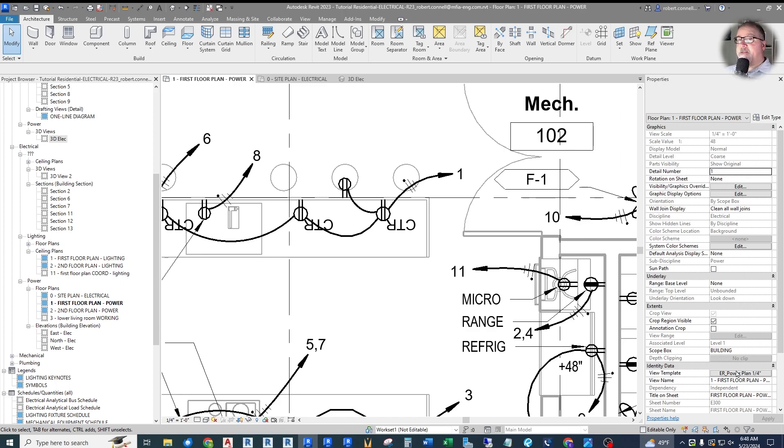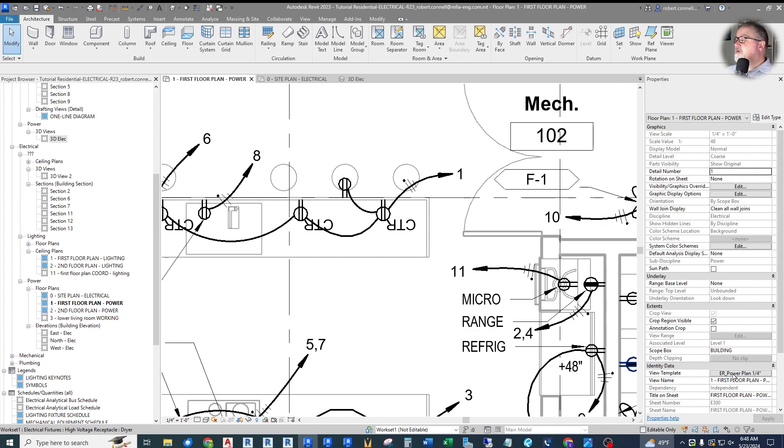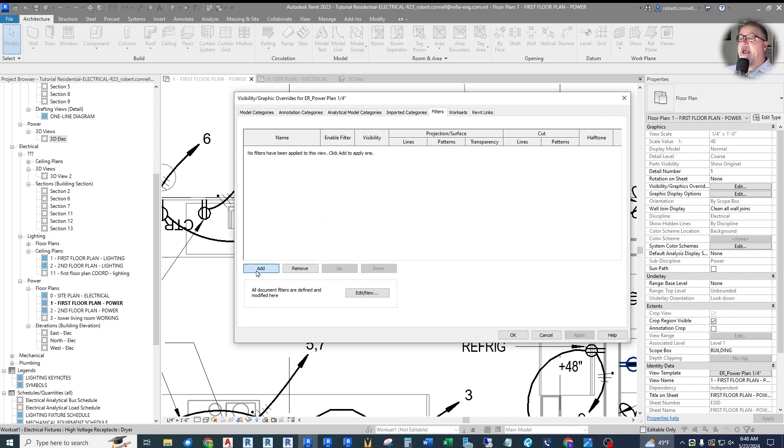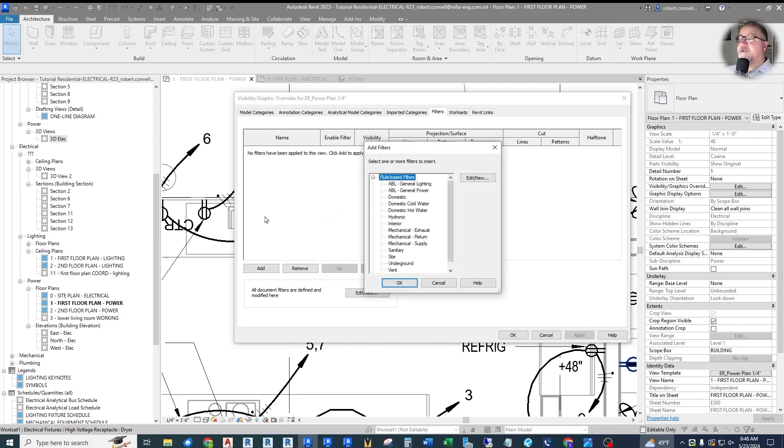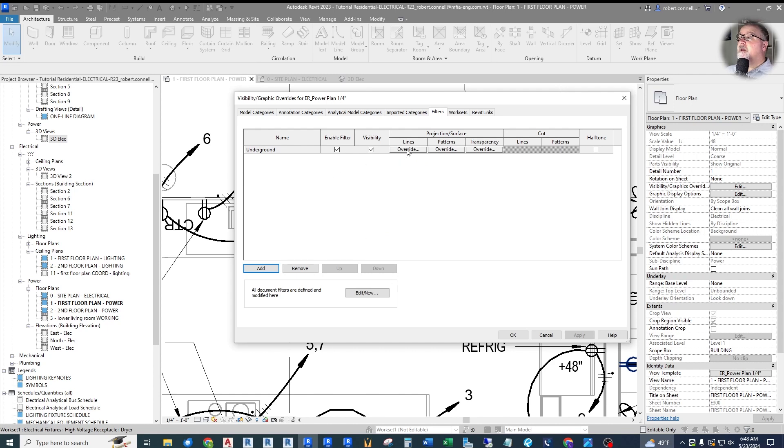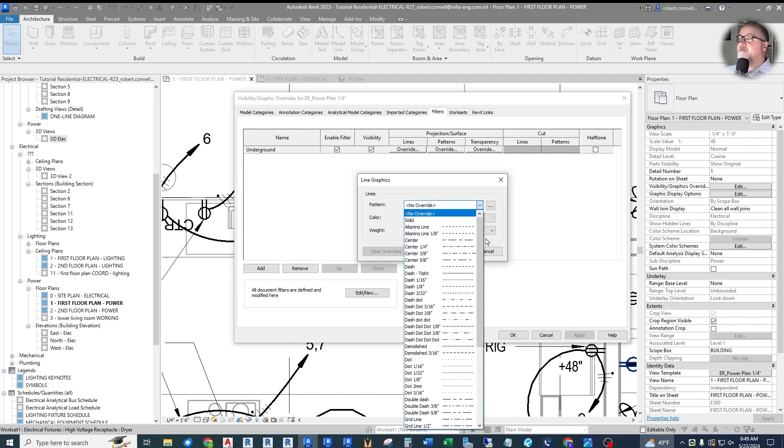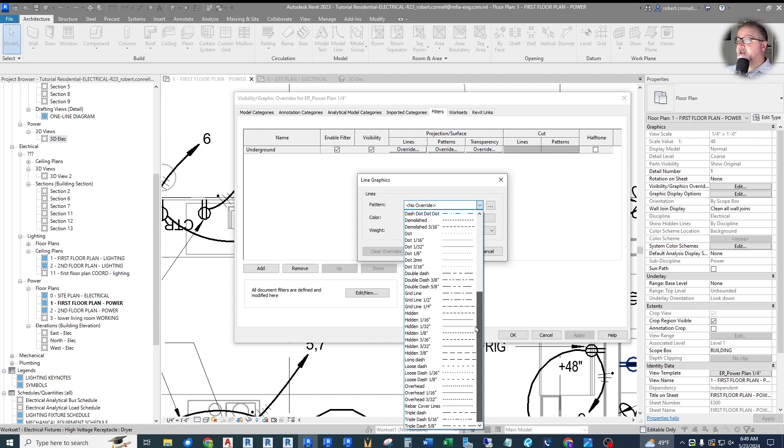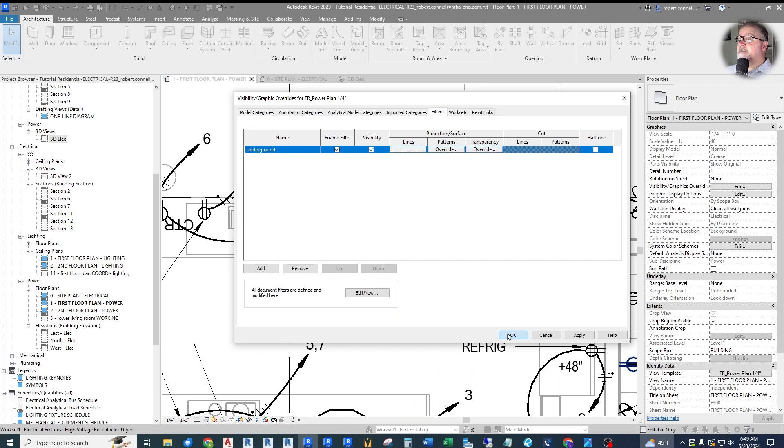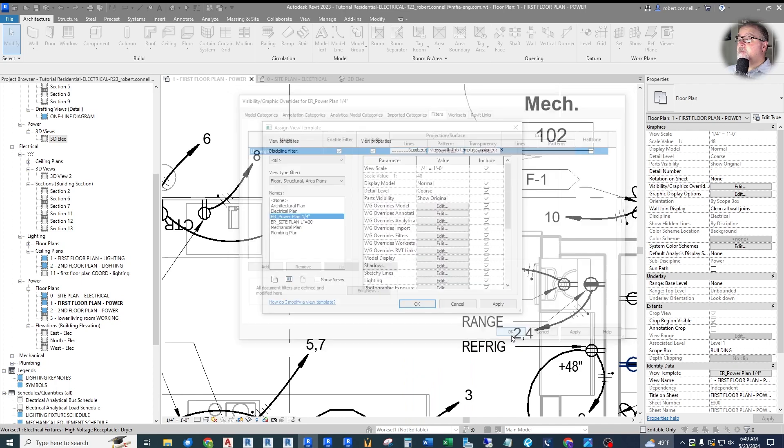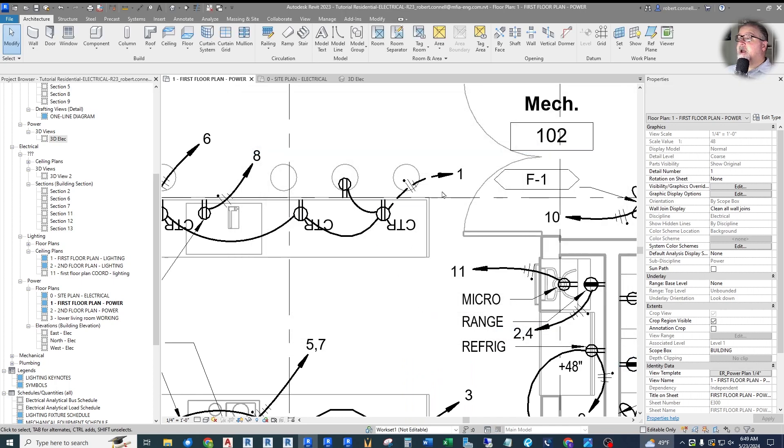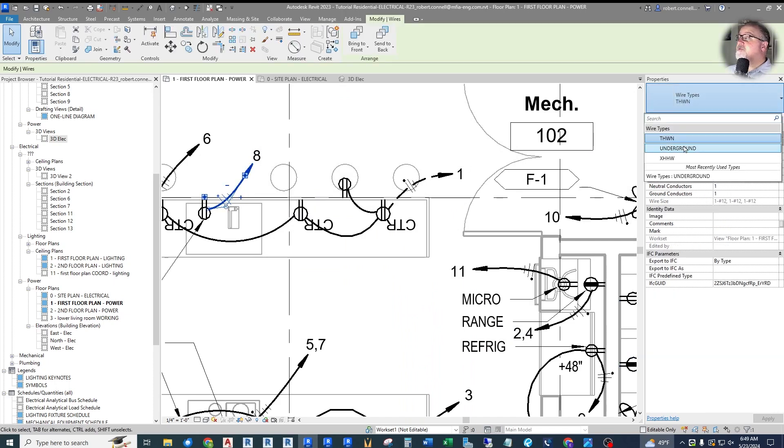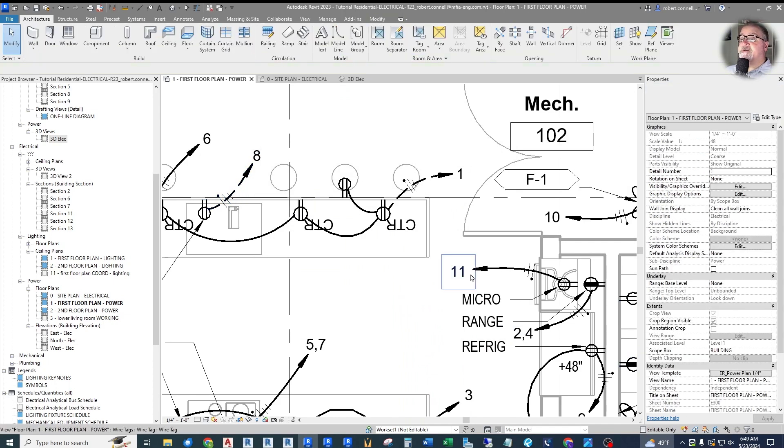Why not? Well, the filter was applied to the site plan view template. So we need to apply that same filter. It's already made, but we need to apply it to this view as well. So under view template power plan, we're going to go into the filters and we're going to add that filter. It's already created. We're going to add the underground filter. And we also want to set its override. I'm going to use the same type of look, hidden eighth.